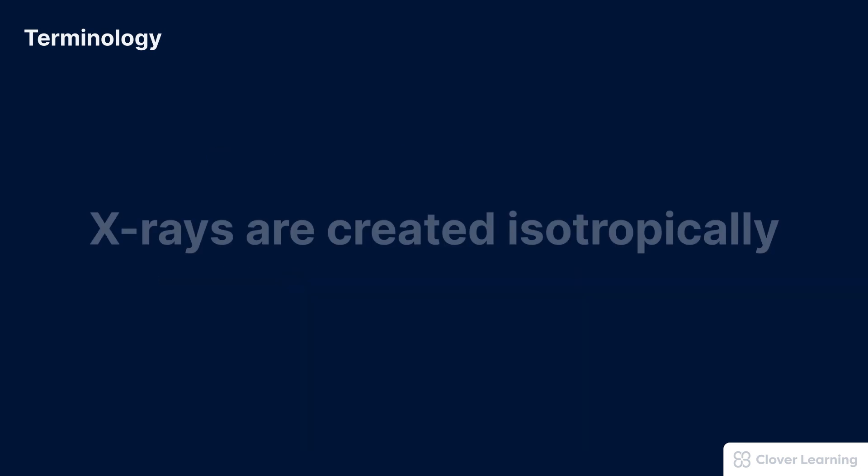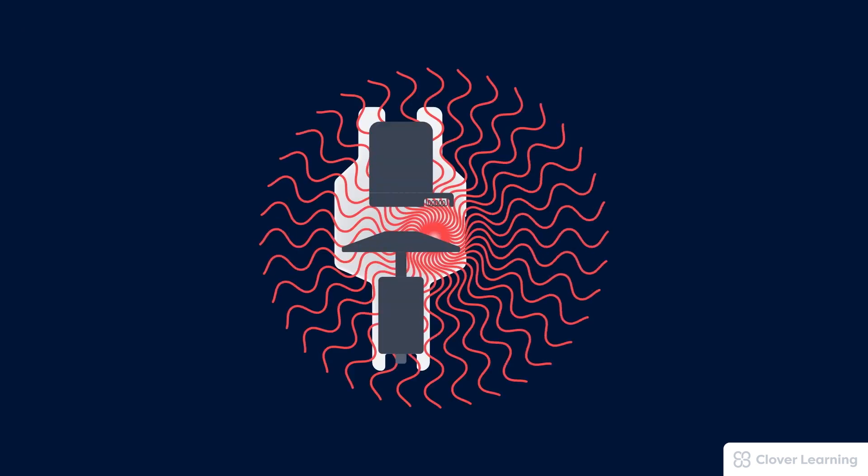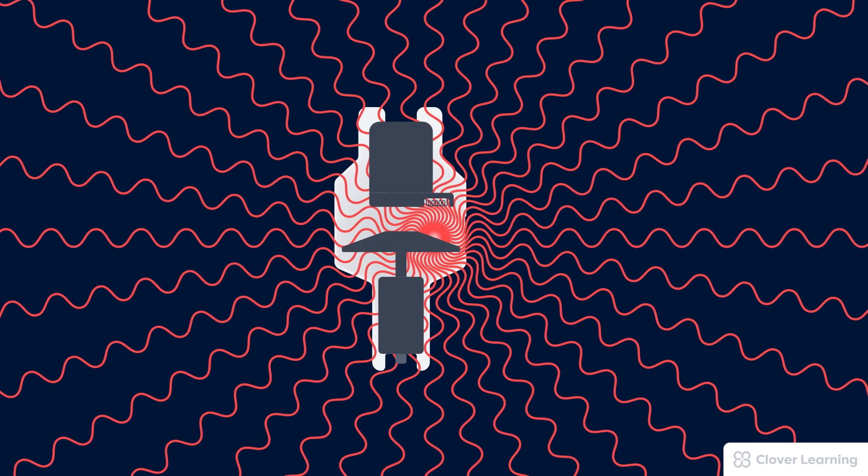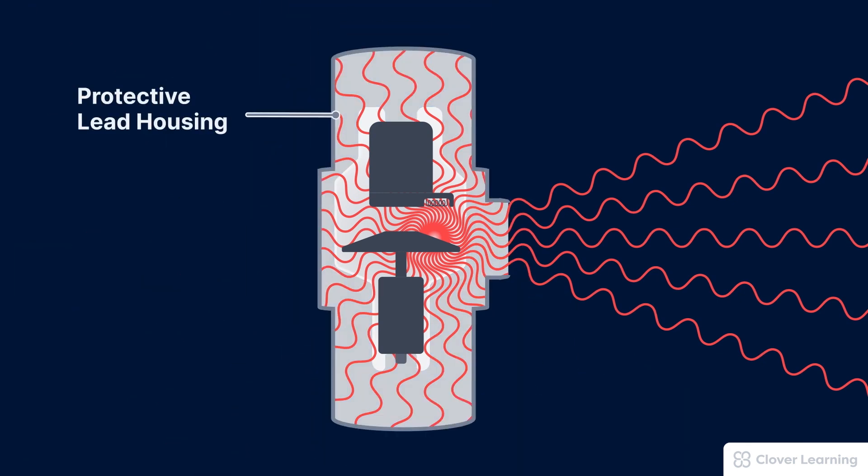Finally, one more thing we should know about x-rays is that when they're created in the x-ray tube, they are created isotropically. Isotropic means that x-rays diverge equally in all directions. In fact, this is exactly why the x-ray tube assembly requires a protective lead housing. The lead housing absorbs all of the extra x-ray photons that we don't actually need. X-rays travel in straight lines, so they will keep on going until we put something in the way to stop them.